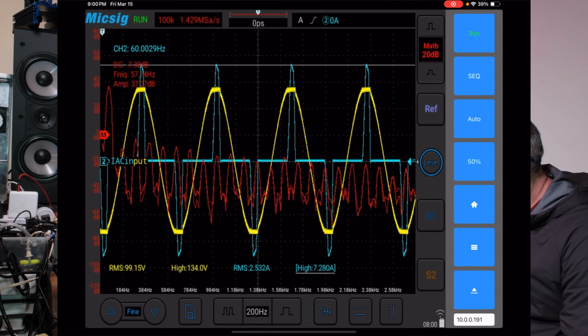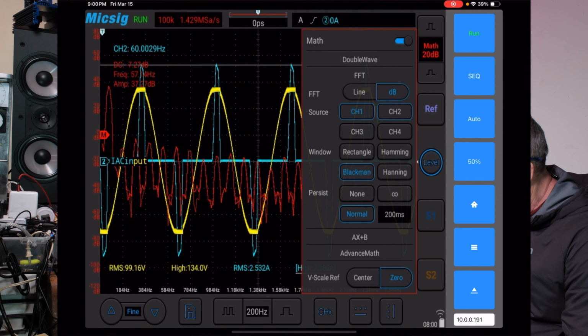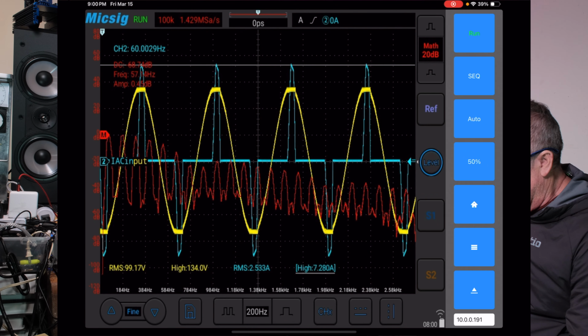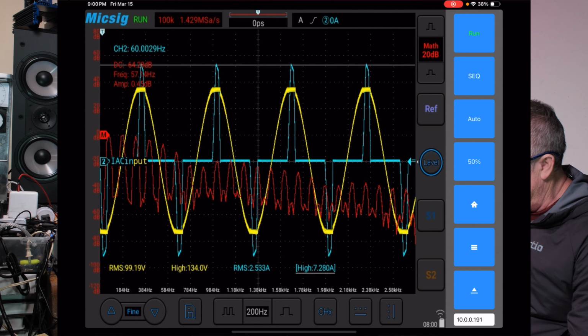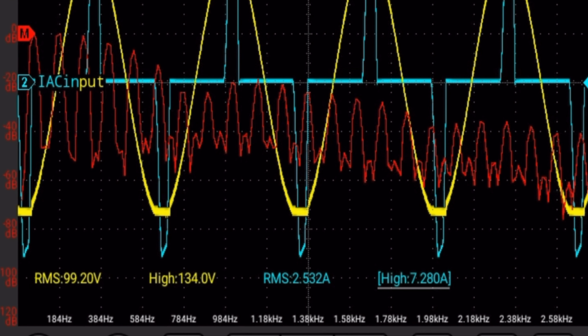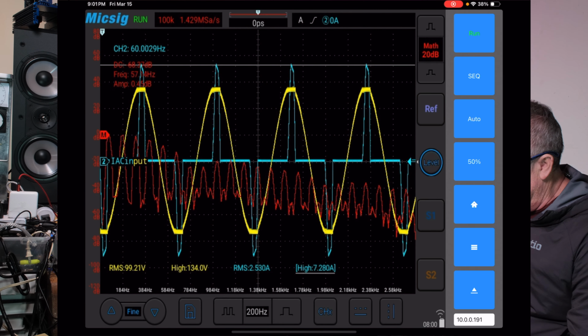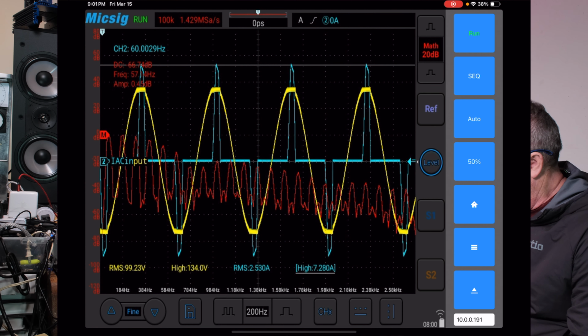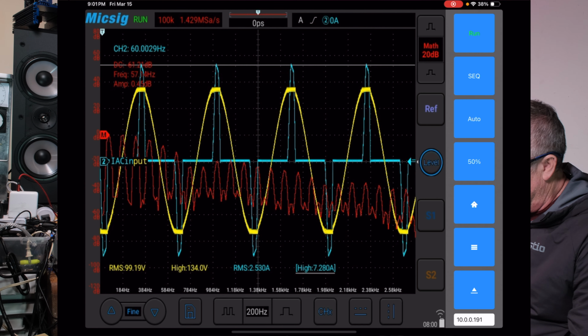Okay, now let's look at the current. Same thing, current still terrible, right? Just like before, it's a big old pulsating current. That is not 60 hertz - well, it's at 60 hertz, the main cycle, but it's because of the straight edges and the flat edges at the bottom in between pulses, it's more of a trapezoidal or square wave versus a sinusoidal wave.